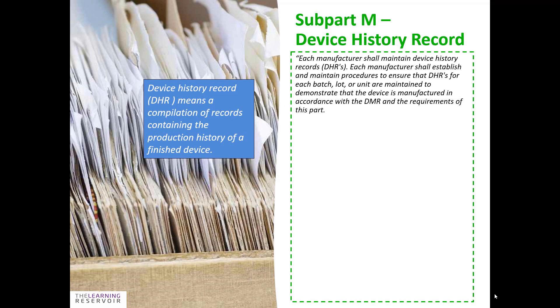So, device history record — what is it? A device history record means a gathering of records containing the production history of a finished device. It states in the regulation that each manufacturer shall maintain device history records, and each manufacturer shall establish and maintain procedures to ensure that the DHRs for each batch, lot, or unit are maintained to demonstrate the device is manufactured in accordance with the device master record and the requirements of the part.